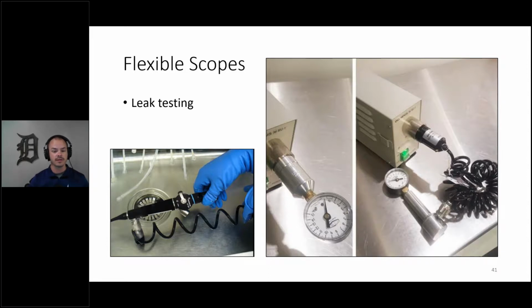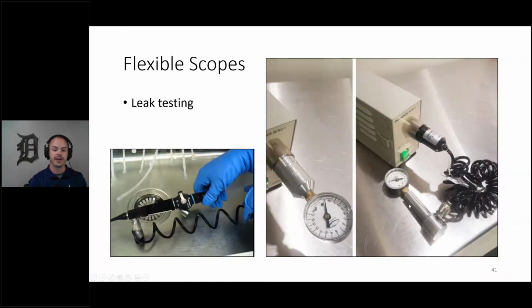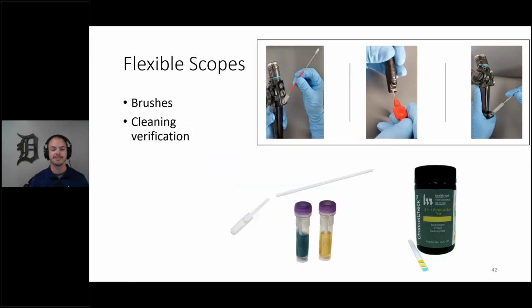Luckily there are devices like you see here in the picture. It's a leak tester, and what it does is help measure the amount of air pressure coming out of the leak tester itself. Then, after the air is pushed through that cord that hooks up to your endoscope, both components are extremely important. Having low pressure reach your endoscope is going to help you miss potential leaks and potential dangers, leading to possible infection control issues. So let's make sure we're checking that leak tester.